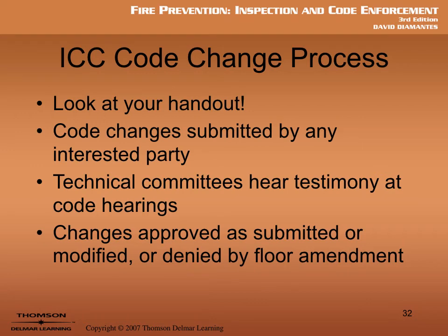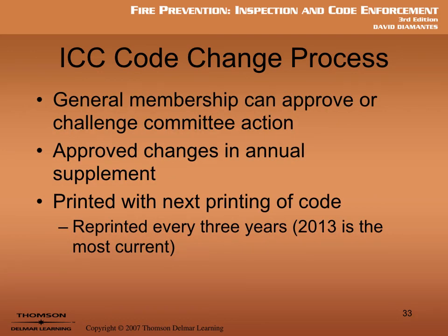So how does this ICC code process happen? Well, I'm going to put a handout on Canvas for you that you can look at. But the code changes are submitted by any interested party. Then it goes to technical committees like we talked about before, and they hear testimony and discuss this at code hearings. Then they make the changes, and they're approved as submitted or modified or denied by floor amendment. Then the general membership gets the chance to vote on it after it comes out of committee.